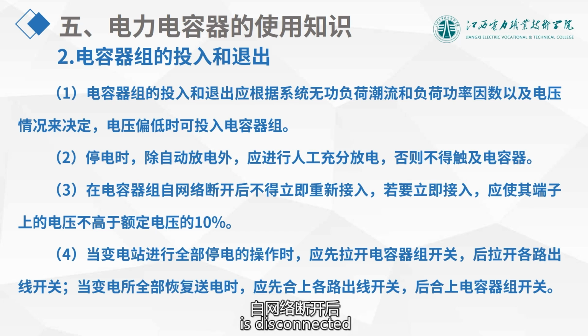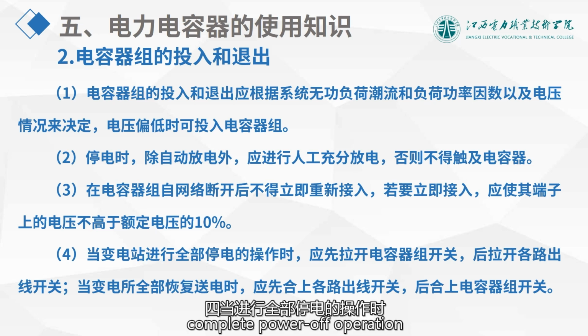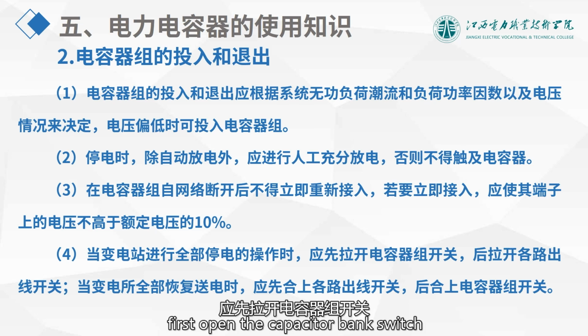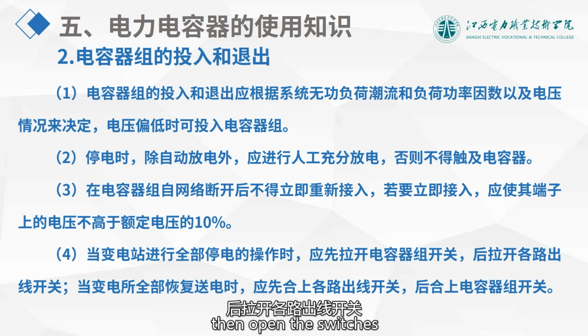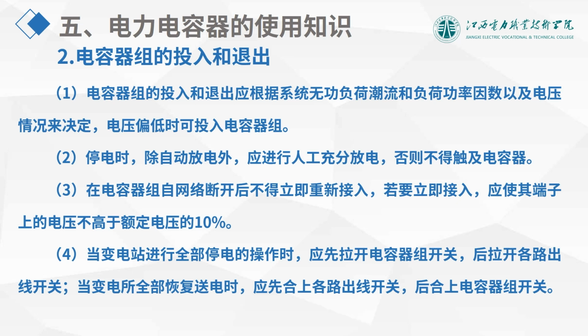After the capacitor bank is disconnected from the network, do not reconnect it immediately. If immediate reconnection is necessary, ensure that the terminal voltage is not higher than 10% of the rated voltage. When performing a complete power-off operation, first open the capacitor bank switch, then open the switches of each outgoing line. When restoring power, first close the switches of each outgoing line, then close the capacitor bank switch.